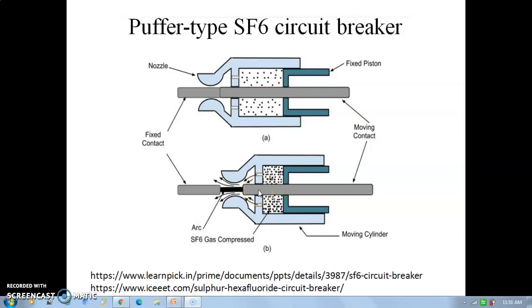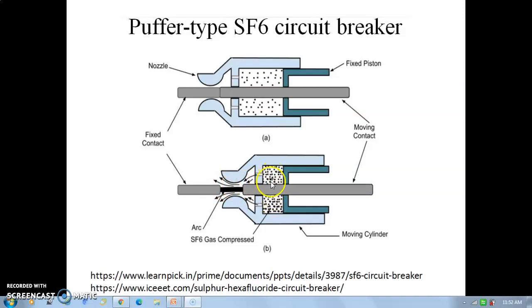Due to the movement of the cylinder, the SF6 gas starts getting compressed because the piston is fixed. There are nozzles provided. Gas is filled between the piston and movable cylinder, and that compressed gas comes between the two contacts.